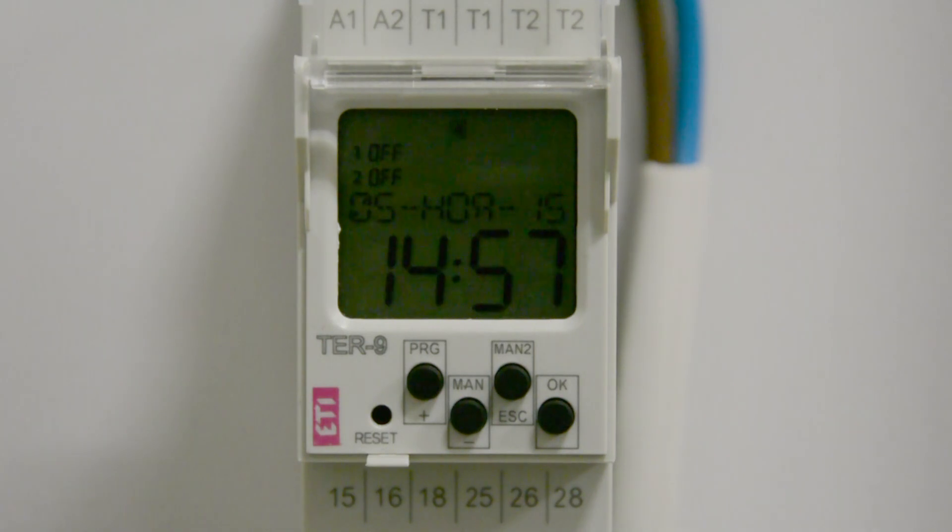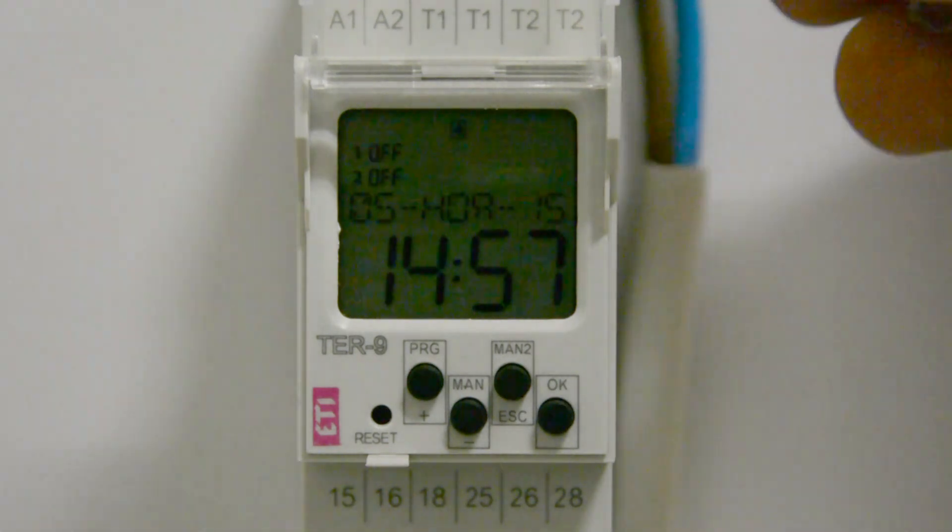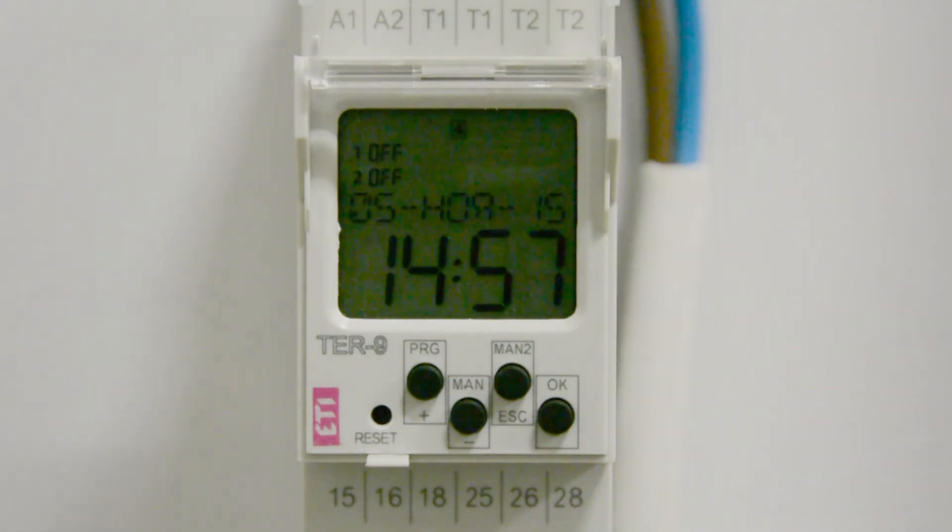This device provides a choice of weekly and annual programs. It has two inputs for connecting temperature sensors and two changeover contacts for each channel. In the case of using one temperature sensor, it is necessary to connect a 10 kOhm resistor to the second input.